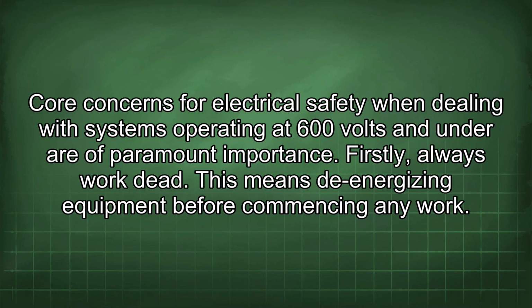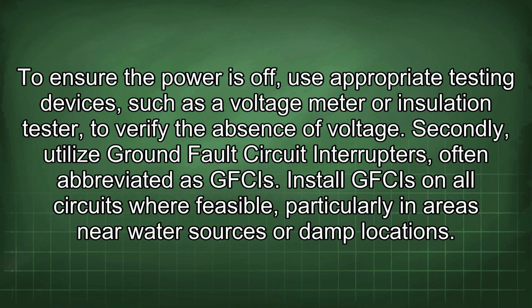Core concerns for electrical safety when dealing with systems operating at 600 volts and under are of paramount importance. Firstly, always work dead. This means de-energizing equipment before commencing any work. To ensure the power is off, use appropriate testing devices such as a voltage meter or insulation tester to verify the absence of voltage.